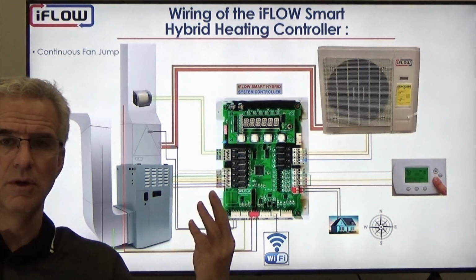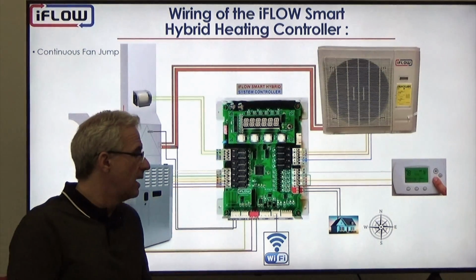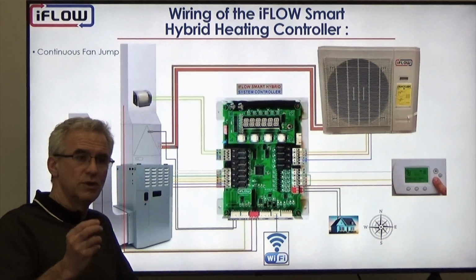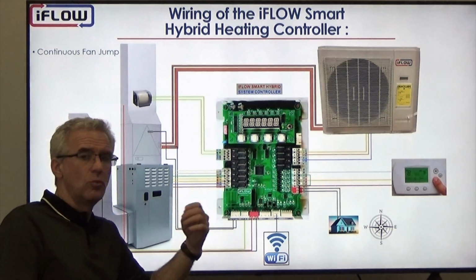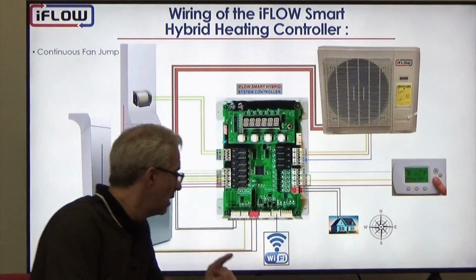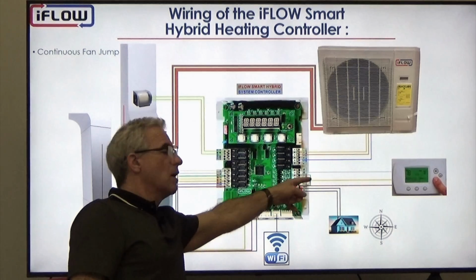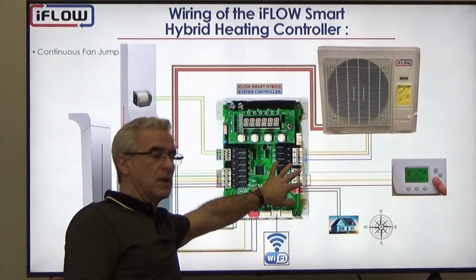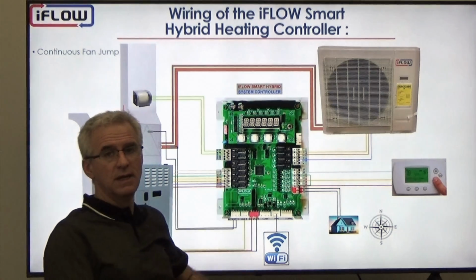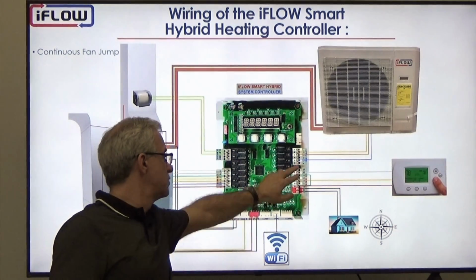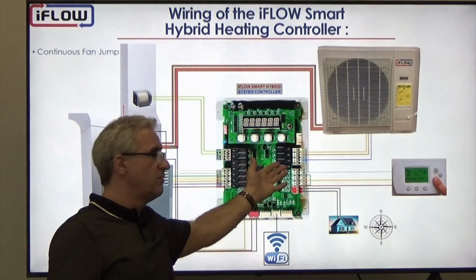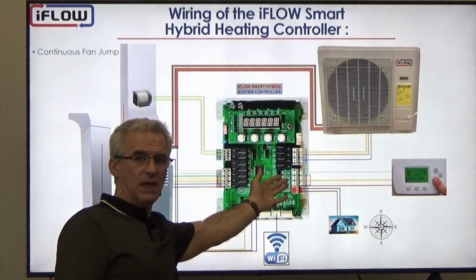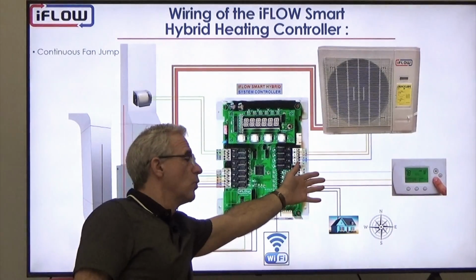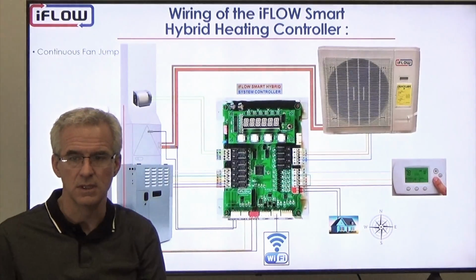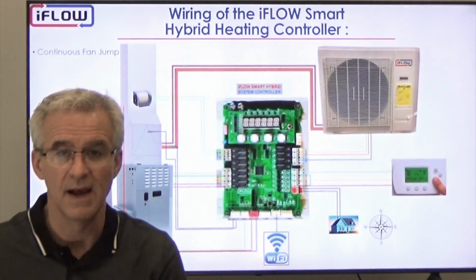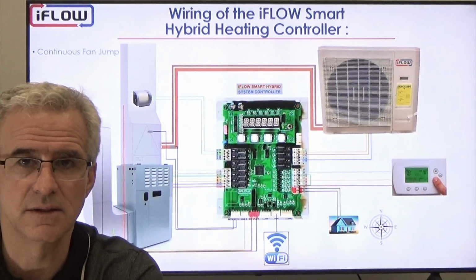So because we only have 3 wires in this example, we won't have a G wire, which is your fan on. But if the homeowner wants that continuous circulation, we could actually just jump R to G at the controller, and they would get full continuous fan operation just by jumping that. So we can effect that feature with the controller in the mechanical room and not worry about having to wire that in or have the additional wires coming from the thermostat to the mechanical room.